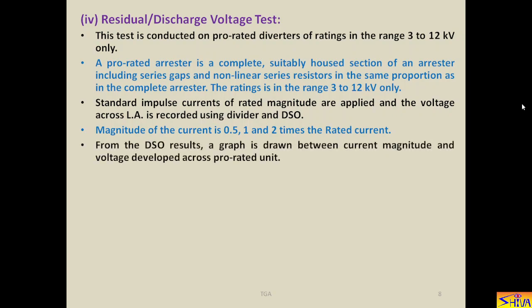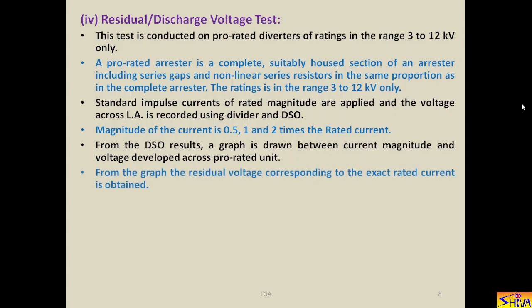From the digital storage oscilloscope results, a graph is drawn between current magnitude and voltage developed across the prorated unit. So this current will be nothing but the discharge current plotted along the x-axis, and the voltage being developed will be the discharge voltage or residual voltage, plotted against the y-axis. So we are having results at 0.5 times the rated current, full rated current, and 2 times the rated current. From the graph, the residual voltage corresponding to the exact rated current is obtained, that is by extrapolation.